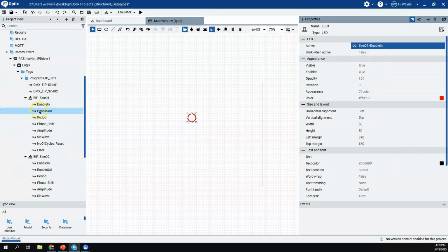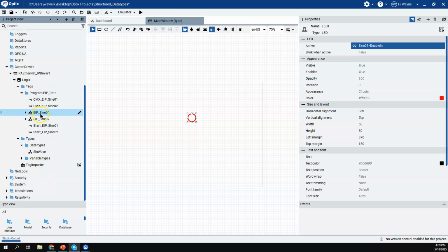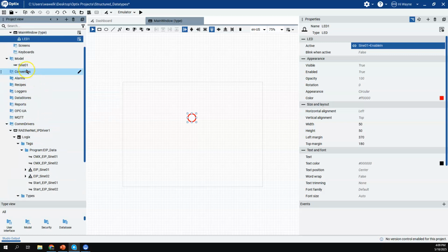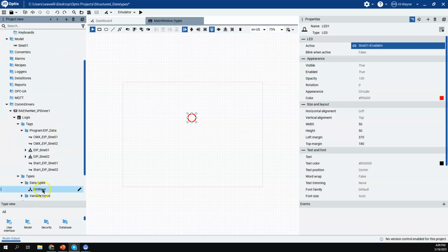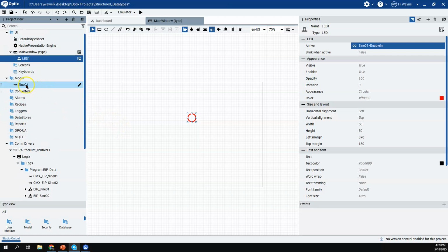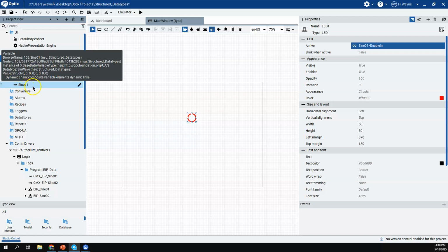Right, so again, under the Logix controller, we have the structured variable, the UDT structured variable comes in, right? And I of course could use it direct from the controller, but if I needed to map it to the model folder, the easy path now is to create a variable and then make it a data type that matches the UDT that comes in from the controller. And again, in 1.16, this works with both the controller tags, as well as if you're bringing in data from an OPC UA server.